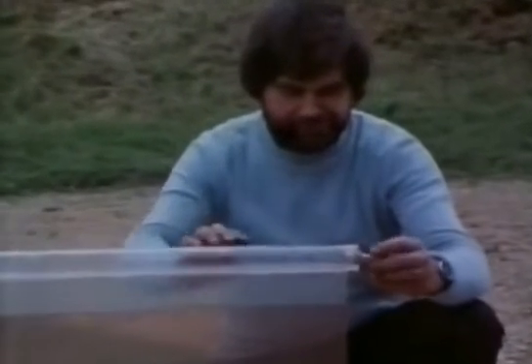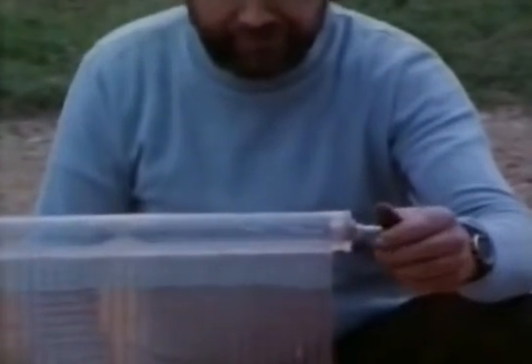Here Rex has made a transparent radiator, so you can see what happens inside. The hot water, fresh from the boiler, builds up at the top, and then as it gives out its heat, slowly falls until it goes through the outlet and back to the boiler. Although radiators are simple things, they can stop working. Air can become trapped inside, and this stops the circulation. This is why radiators have bleed valves on top.